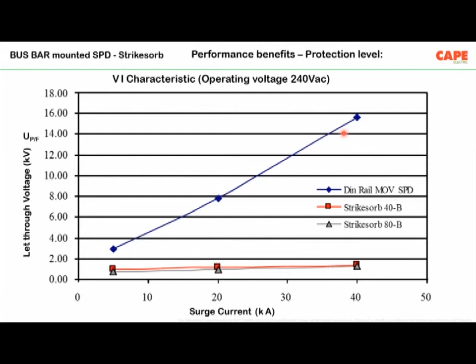So the problem of DIN rail mounted SPDs is that when the rate of change of current is higher and higher, more voltage drops on the connecting wire. As a result, most probably these devices won't protect your electronics. So you need to have a really good quality product or good system like the bus bar mounted SPDs.